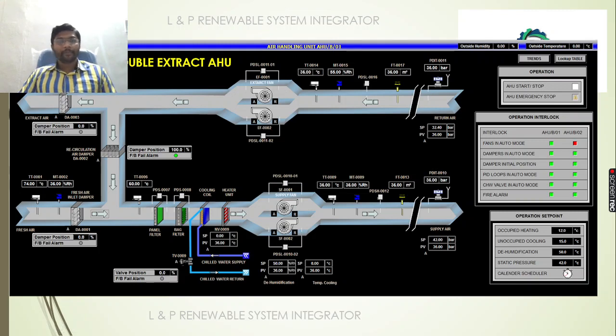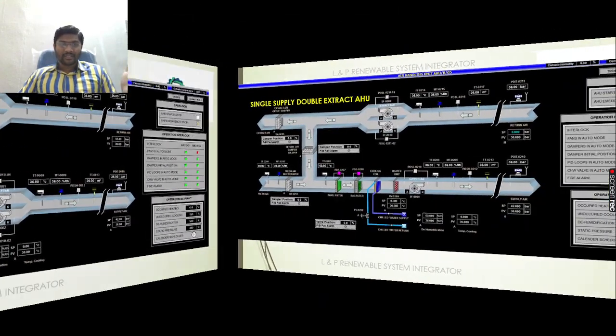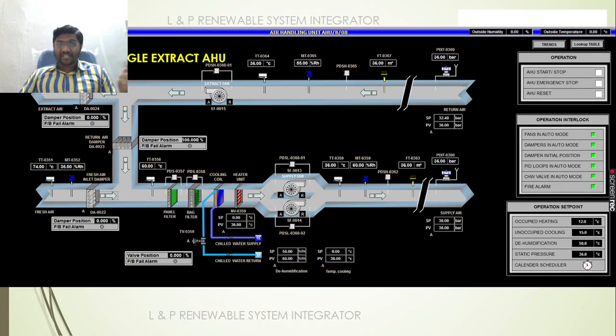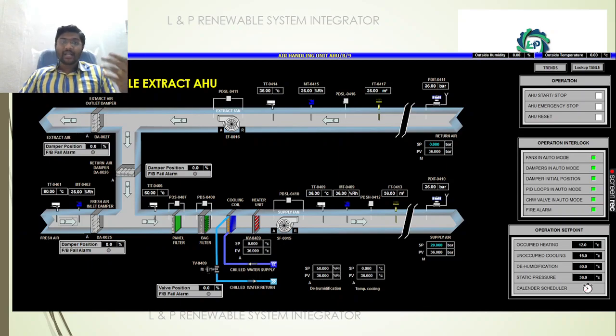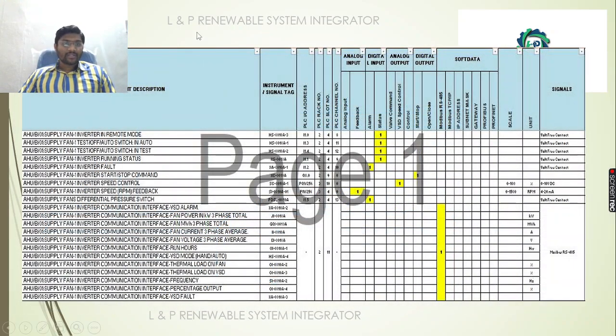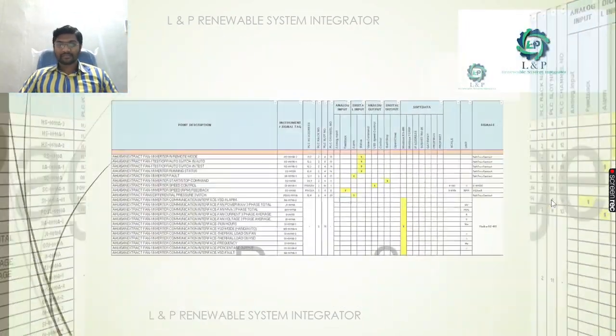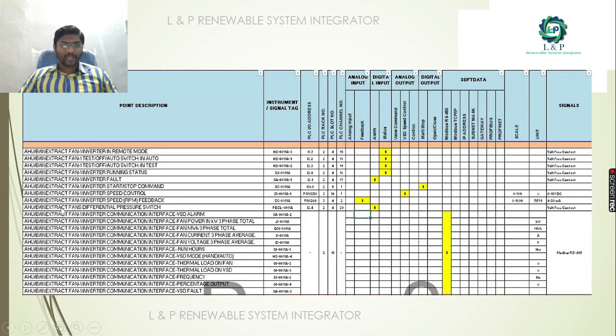Regardless of AHU type — double supply double extract, single supply double extract, double supply single extract, or single supply single extract — differential pressure switches can be installed. From a monitoring standpoint, the signal is a digital input. On the supply fan side, the differential pressure switch provides a digital input that can be treated as an alarm — it is a volt-free contact. The same applies to the extract fan side.